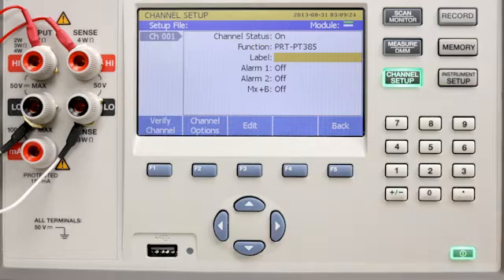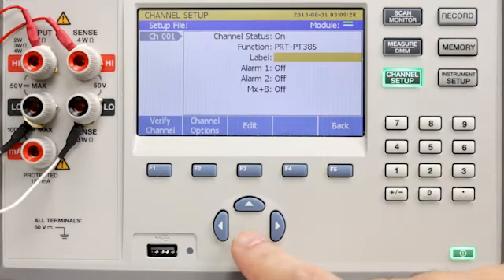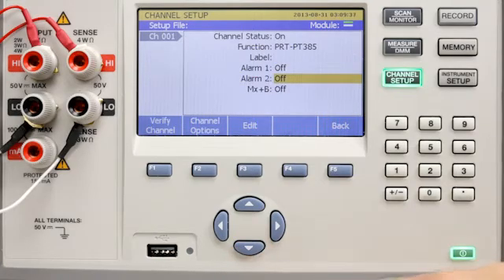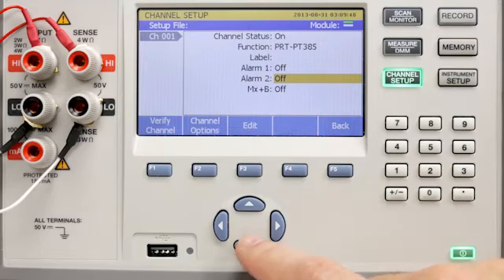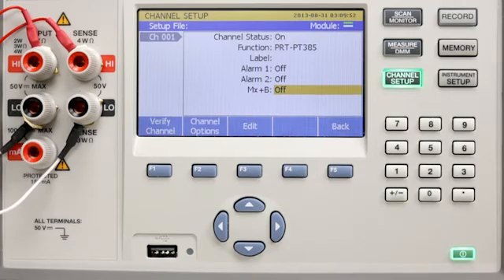We can apply a label to this channel which is recorded in the data file. You can enter a label through the navigation keys and the alphanumeric pad. You have the ability to set two alarms on each channel. These alarms indicate when either an upper or lower range has been exceeded. The alarms can output a signal from the rear panel output to an external device. And all channels have the ability to do an MX plus B, which is a gain and offset for scaling of various signals.